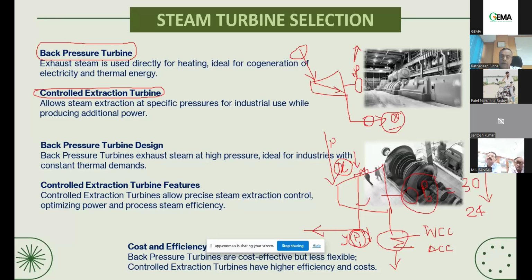And in this case also, that is how it works, but the cost of the control extraction turbine is high, so the capital cost is high. However, because I am condensing here, I am putting some amount of heat to the atmosphere through cooling tower or ACC, so the overall efficiency will be low. At the same time, just to highlight, though it's not important for ethanol plant in that sense, sometimes it may be important.